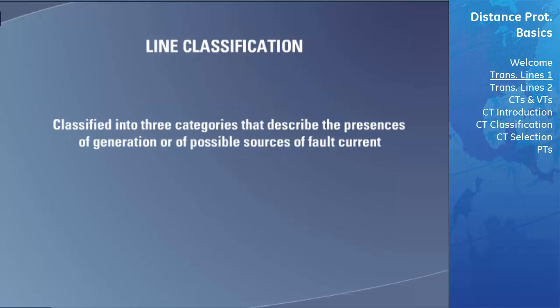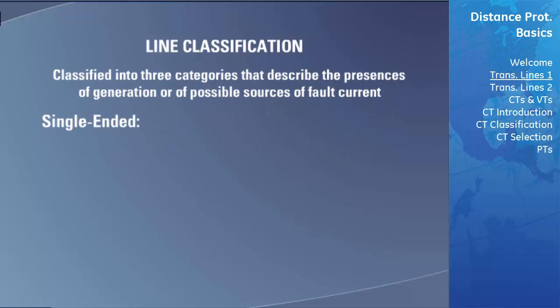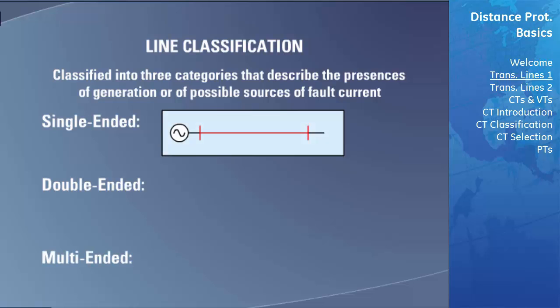Transmission lines are classified into three categories that describe the presence of generation or of possible sources of fault current that might be found at the transmission line's boundaries. These are single-ended, double-ended, and multi-ended. A single-ended line, also called a radial line, has a source at only one end. This type of line is used to deliver power from the source to a load at the other end. Whenever a fault occurs, there is only one source of current to feed the fault.